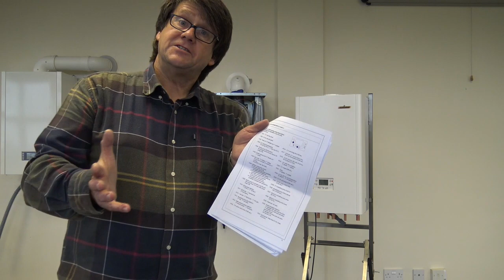You can set your central heating fan speeds through the parameters, and your hot water fan speeds. You can have the keypad disabled or on. One of the parameters is the maximum temperature on central heating, which is 50 degrees C and cannot be altered. Do you really need fancy controls? If you oversize the radiators slightly and run this boiler at 50 degrees C, it's condensating wherever it's running - it's amazing. I've got mine at home running at 50 degrees C, it's a dream. If your customer's not happy with the temperature, then adjust that parameter. But what I'm saying, guys, is your customer can't tamper with those parameters unless you do.